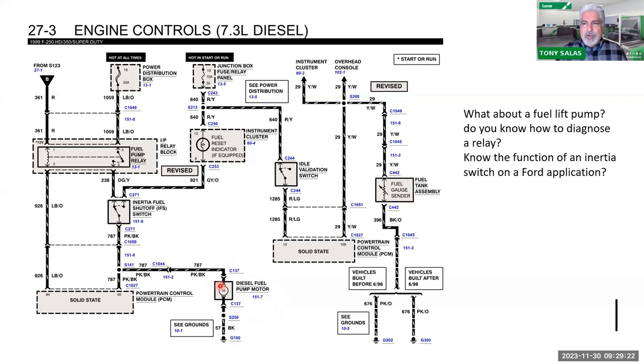You're probably asking how the new motor could be fried. If you understand how a motor draws current, the Watts formula comes into play — volts times amps. So it's going to draw a certain number of watts of power, but if the voltage drops, the amperage goes up. And amperage creates more heat, which can shorten the life of the pump.